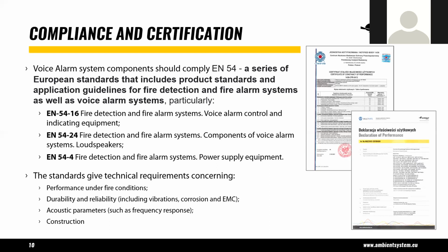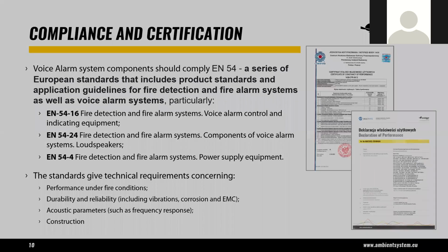So anywhere where you're using a voice alarm system and you're required to meet those codes of practice that we used before, those codes of practice, particularly BS5839 and EN50849, require you to use equipment that holds certification to EN54. So that's the EN54 part, or how the performance and reliability of the systems is defined within the code of practice that we just looked at. So that kind of covers us for the standards and the compliance side of things.